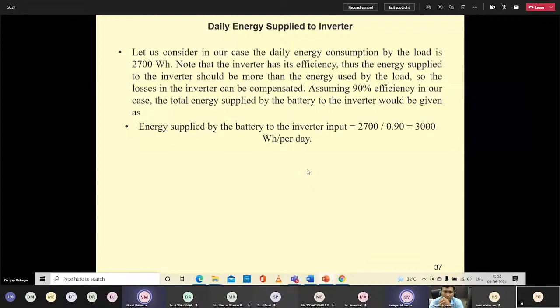I have shown here one case of inverter sizing that I have already discussed, that 25% margin you have to keep for losses. So suppose for a 2400 watt system, if you take a 25% margin, then it should be somewhere near 3000 watts. So you need a 3 kilowatt inverter in case of a 2400 watt load. Now, daily energy supply to the inverter. Let us consider the daily consumption of the load is somewhere near 2700 watt hours. Assuming 90% efficiency, it will give about 3000 watt hours per day.